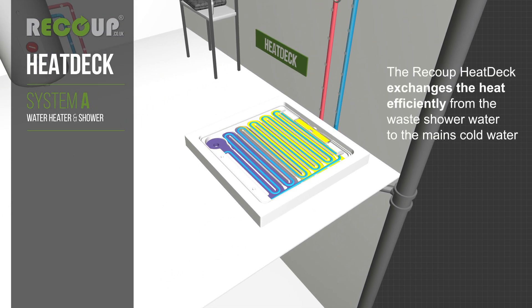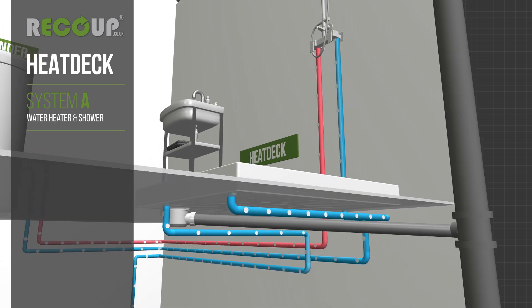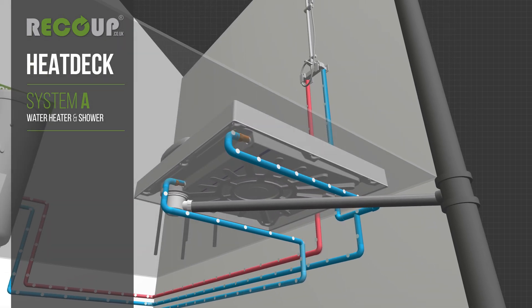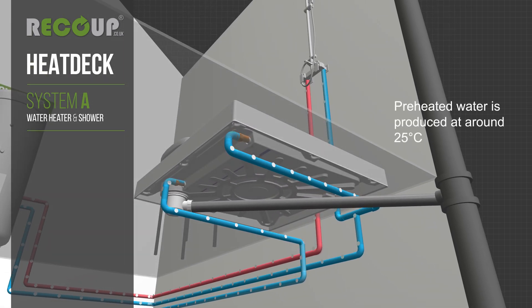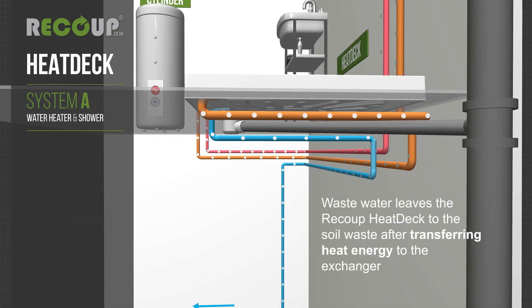The recoup heat deck exchanges the heat efficiently from the waste shower water to the mains cold water. Preheated water is produced at around 25 degrees Celsius. Waste water leaves the recoup heat deck to the soil waste after transferring heat energy to the exchanger.